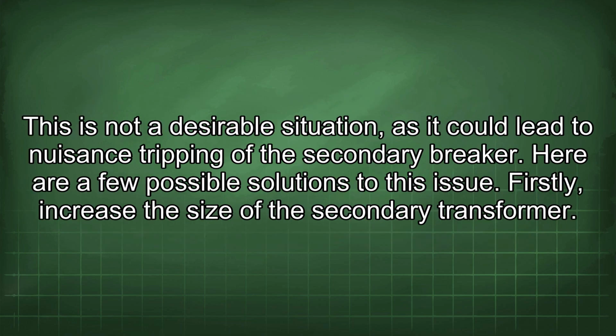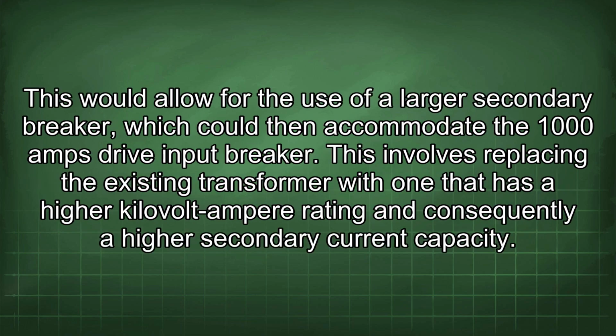This is not a desirable situation, as it could lead to nuisance tripping of the secondary breaker. Here are a few possible solutions to this issue. Firstly, increase the size of the secondary transformer. This would allow for the use of a larger secondary breaker, which could then accommodate the 1000 amps drive input breaker.